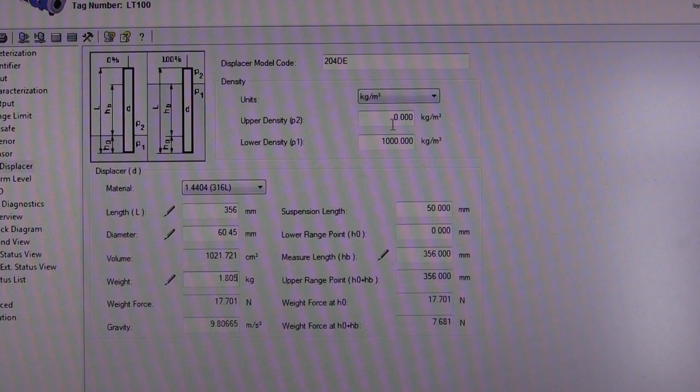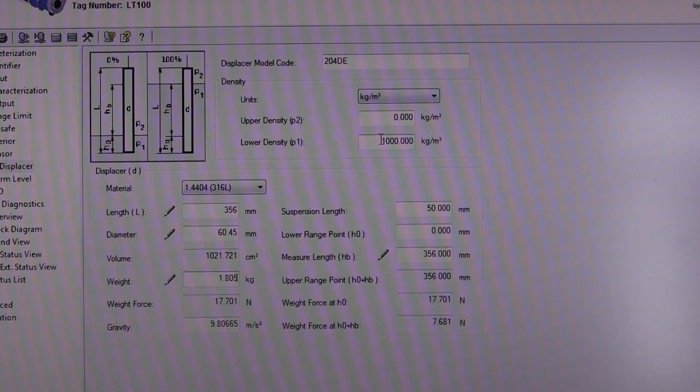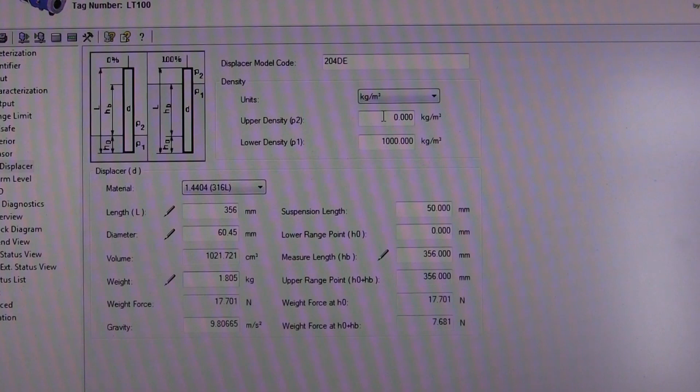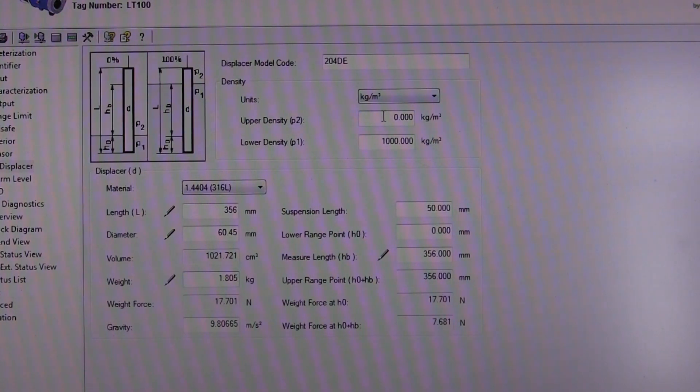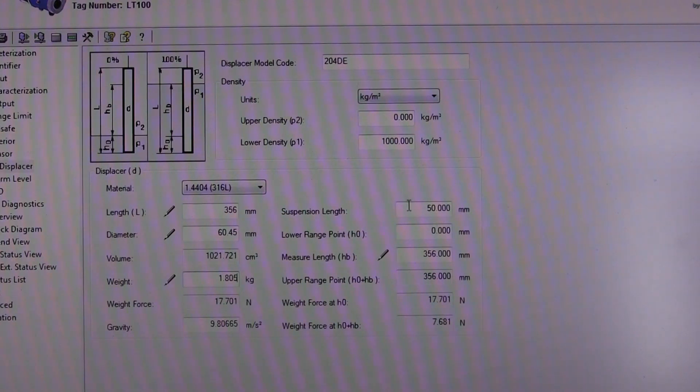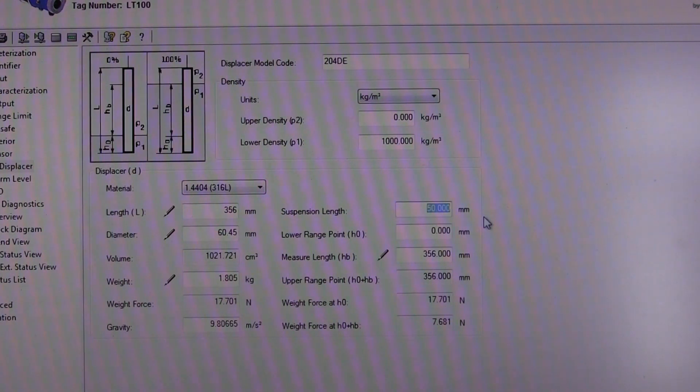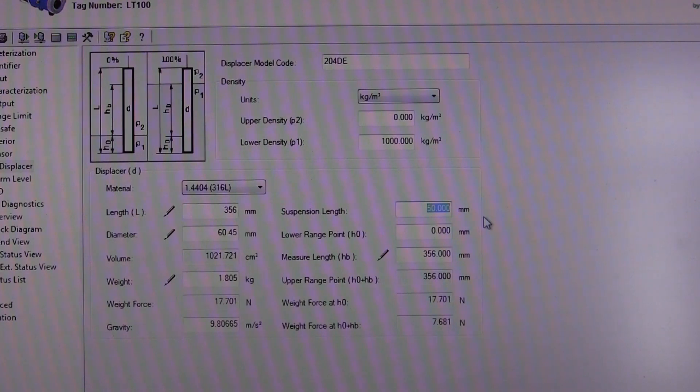We enter our liquid density under lower density. In this case, it's water, so it's 1000 kilograms per cubic meter. The upper density is for the density of air, which for all intents and purposes is zero. Then lastly, we enter the suspension length, which is the length of the chain connecting the displacer to the transmitter.